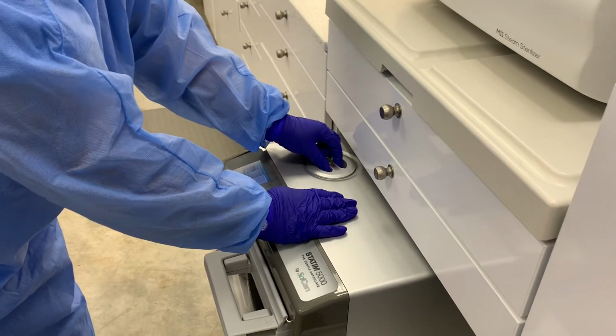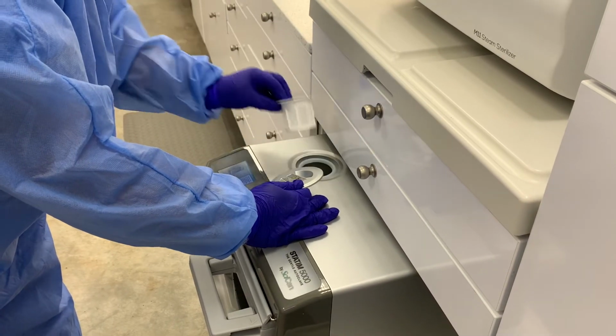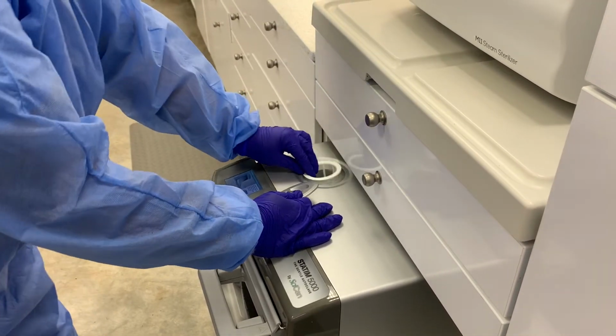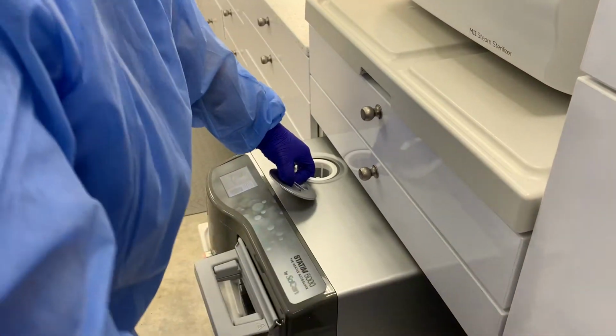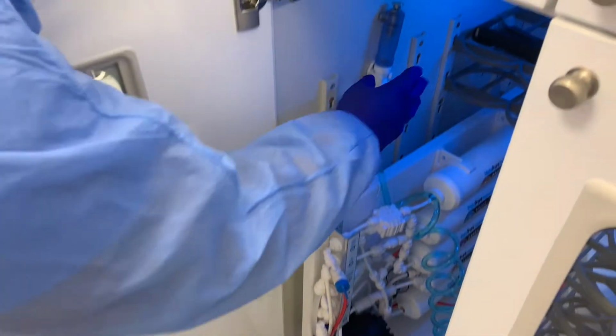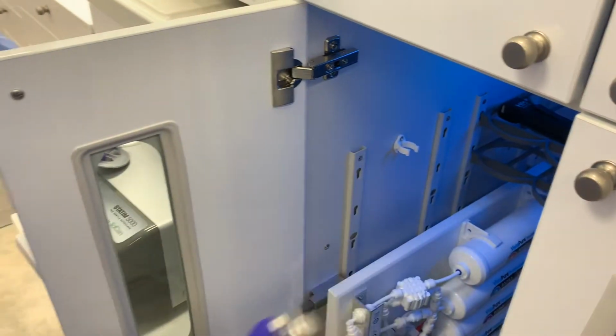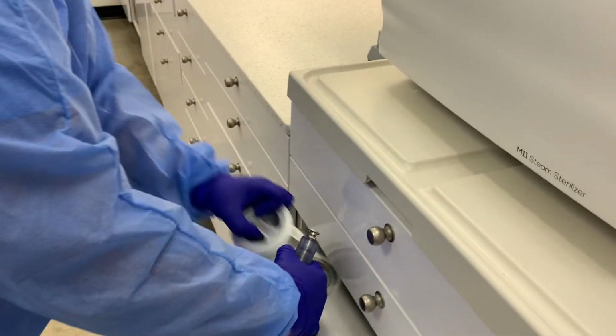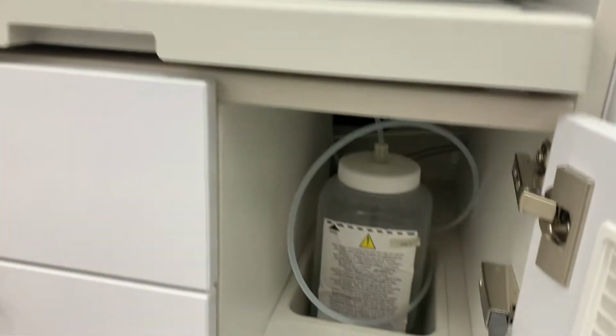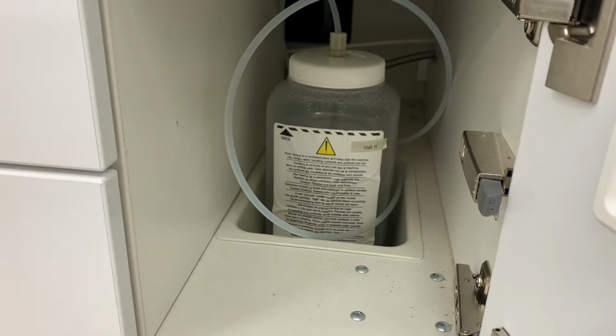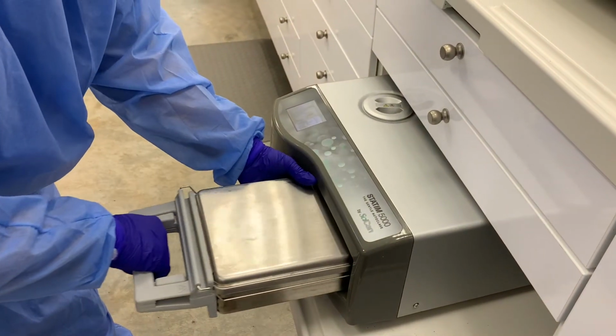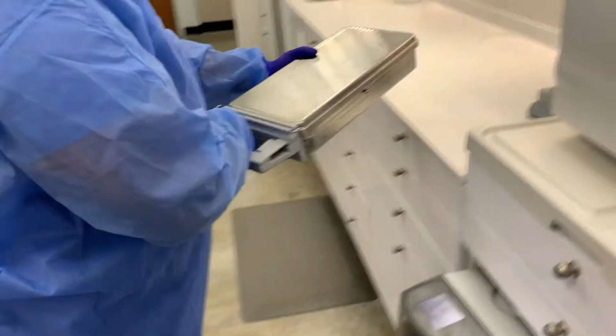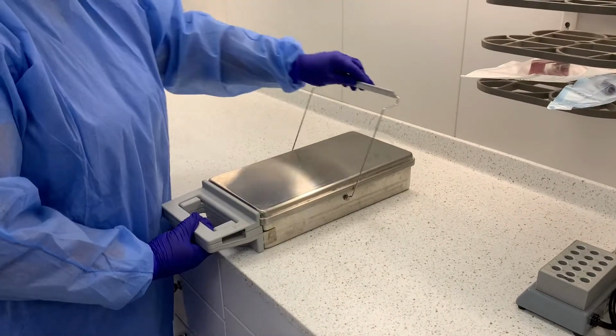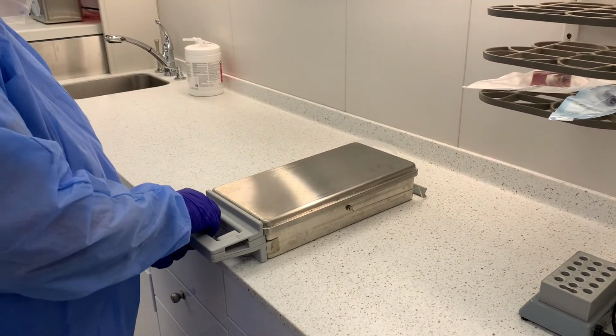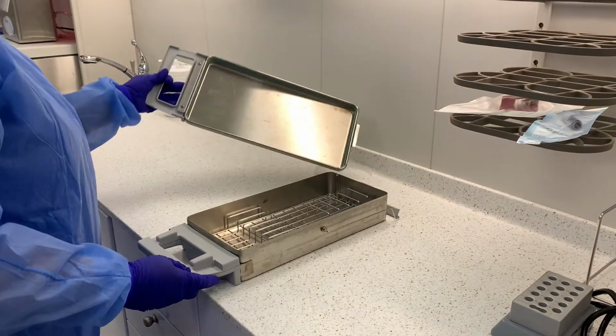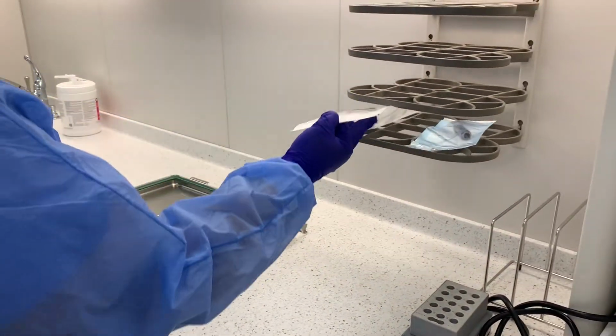Before using the Statim, make sure you check the water levels in the reservoir. The water level in the tank should be in between the maximum and minimum line. If not, take out the drain. The Statim is a sterilizer for instruments that cannot stand the high heat of the autoclave or instruments that are needed immediately. All handpieces and burrs go in the Statim.